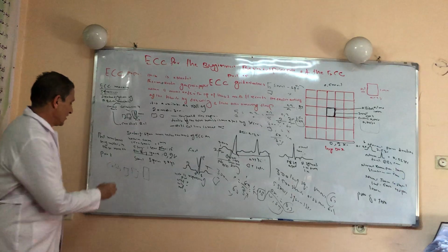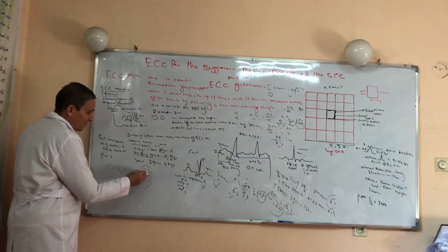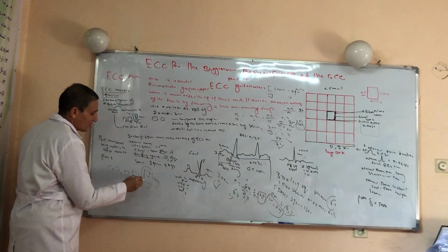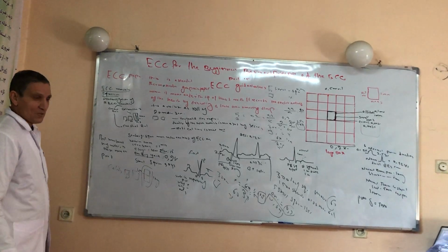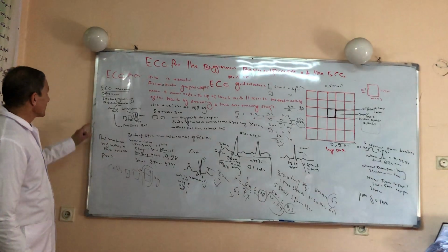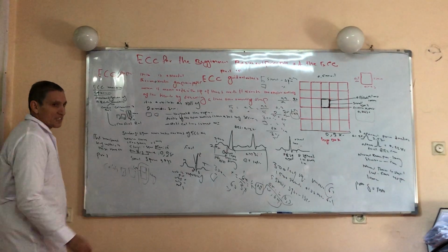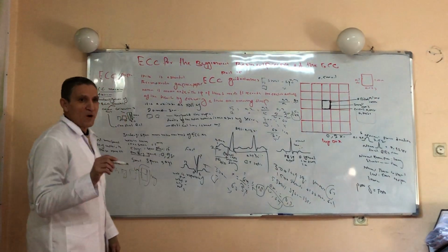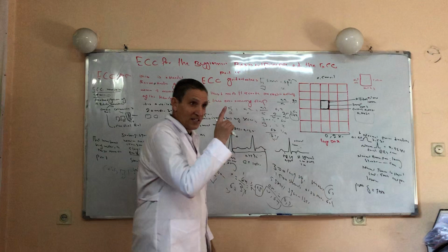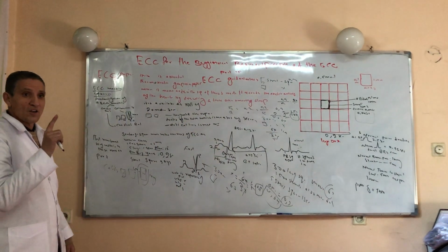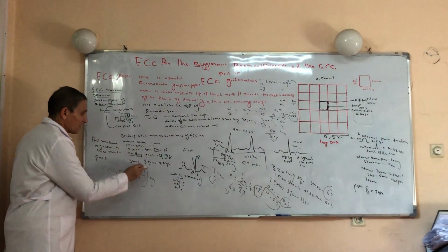Which one is correct? This is the 2 large squares, 10 millimeters in amplitude, which represents 1 millivolt. Standardization of the ECG paper is made by two things: one is constant rate, the second is calibration. A calibration signal is one where a 1 millivolt electrical signal should move the needle of the ECG machine vertically to 1 centimeter, or 2 large squares. This was about the calibration signal.